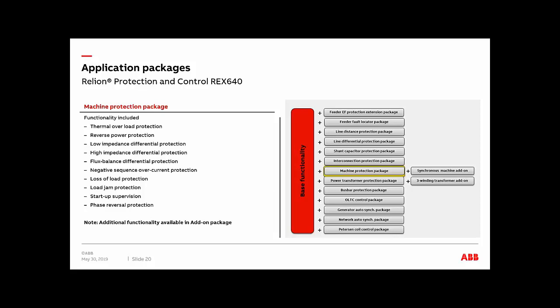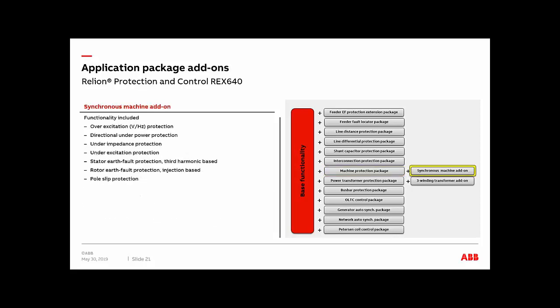Now, we do have an additional package for this one, which we call an add-on package for machine, which is for your synchronous machines in this case, where you can have overexcitation or volts per hertz. You get directional underpower and underimpedance protection. You're going to have underexcitation as well, and stator earth fault protection with third harmonic based, which is able to detect the stator earth fault at the neutral point, at least 15 to 20% from the neutral point along the stator winding. So you're going to get 15-20% from the neutral point into the winding.